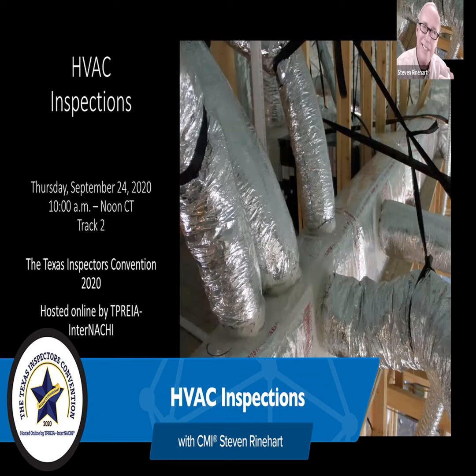Olfactory, looking for gas leaks, basically saying, smell it. You're not required to get a gas detector, though some guys do. If you enter an area where you do lots of gas houses, it's probably worth it to get a gas detector, but you're not required to. And they're talking about the shutoff and access to the shutoff, kind of the same answer they had on a couple of them.